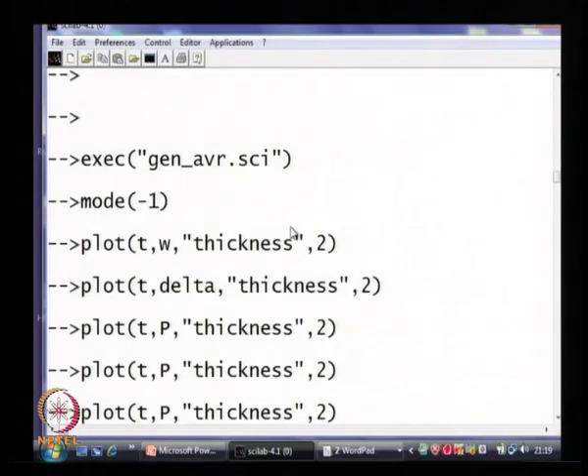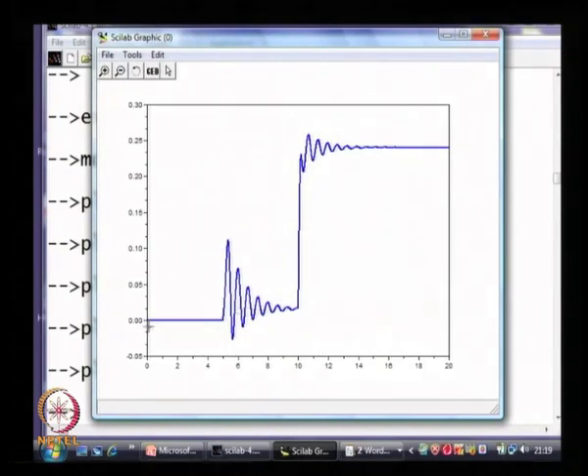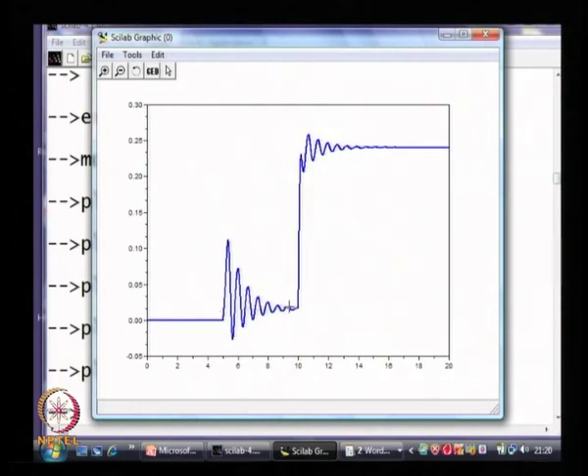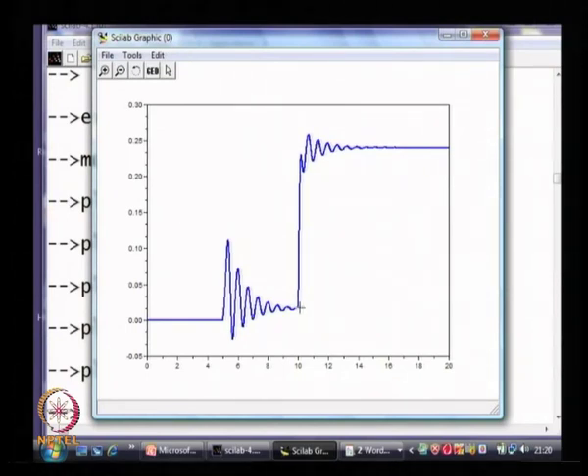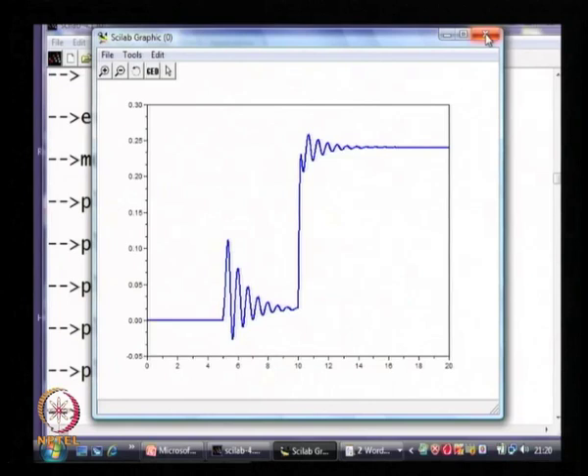If I plot q — the reactive power output of the machine — initially there is no real or reactive power at synchronization. When the mechanical power is changed, the electrical power also changes and EFD changes, so the generator supplies some reactive power. If I change Vref on the other hand, the real power does not change, but the reactive power changes quite substantially. So by changing the reference voltage of the AVR, we are effectively changing the reactive power output of the generator.